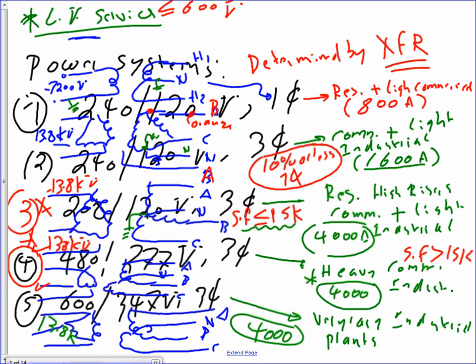So that's system 1. System 2, we have a 240/120 center tap delta. What they give you on the primary side is 13,800 volt. Can you see that? On the secondary side, they give you 240/120 center tap delta, they call it. And I know you guys have got it. The ones who came from electrical, you guys did calculation on this. It's a 3-phase. So what we do, we use it for commercial plus light industrial. We use it if you have a load of up to 10% single phase and 90% 3-phase. This is typically what we use this system for. 10% single phase, and the rest is 3-phase. You can use it very high, up to 1600 amps, and these are all suggestions for the system they use. This is a delta center tap. Can you see how they center tap it right in here? Delta center tap.